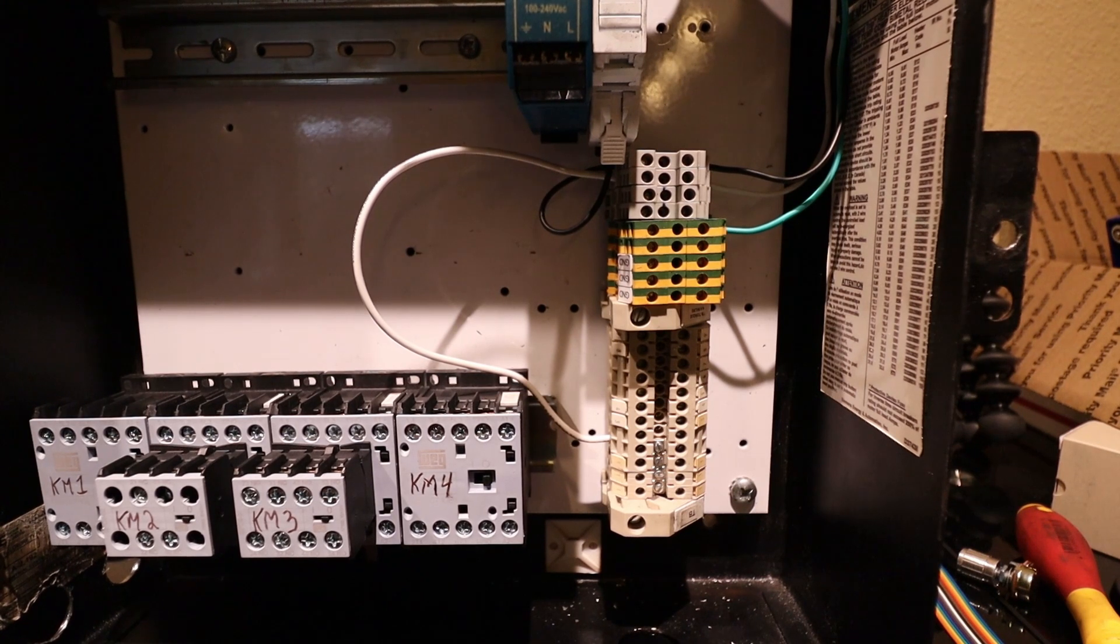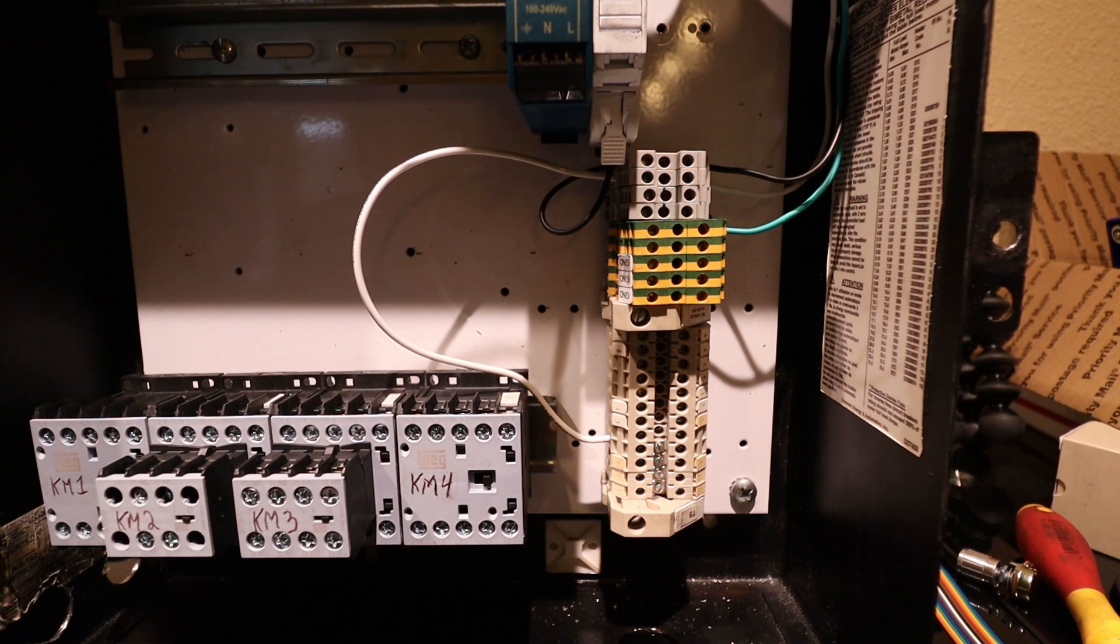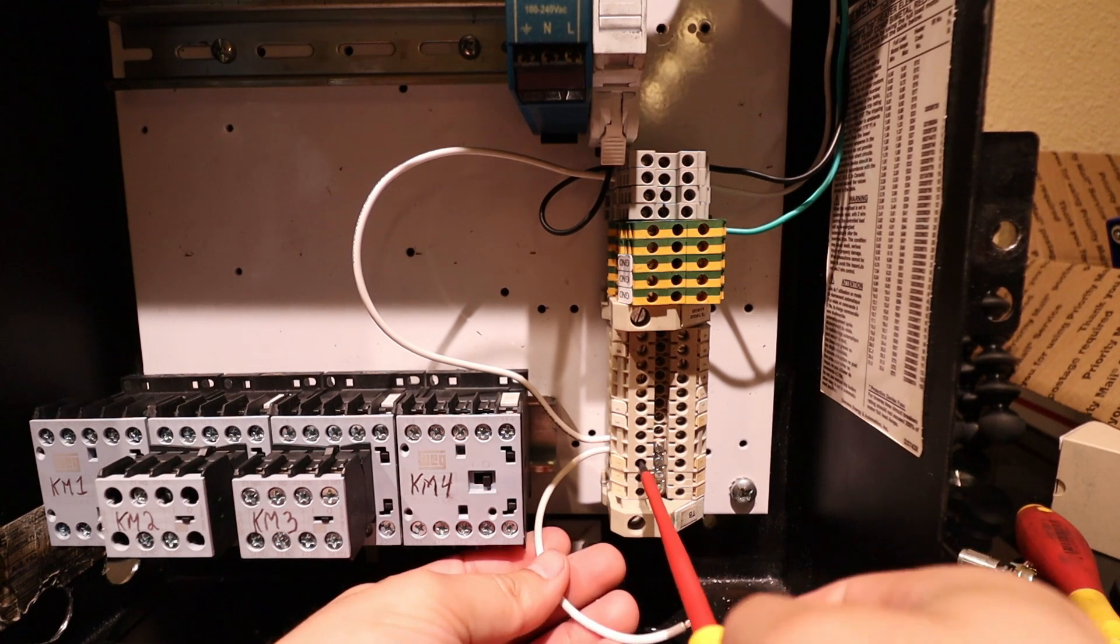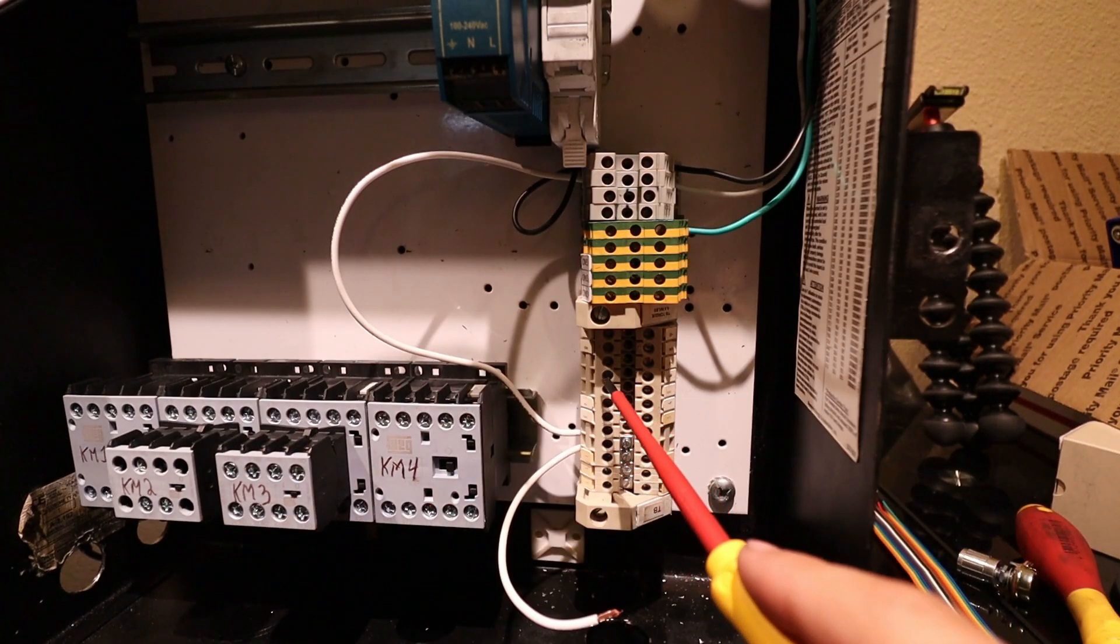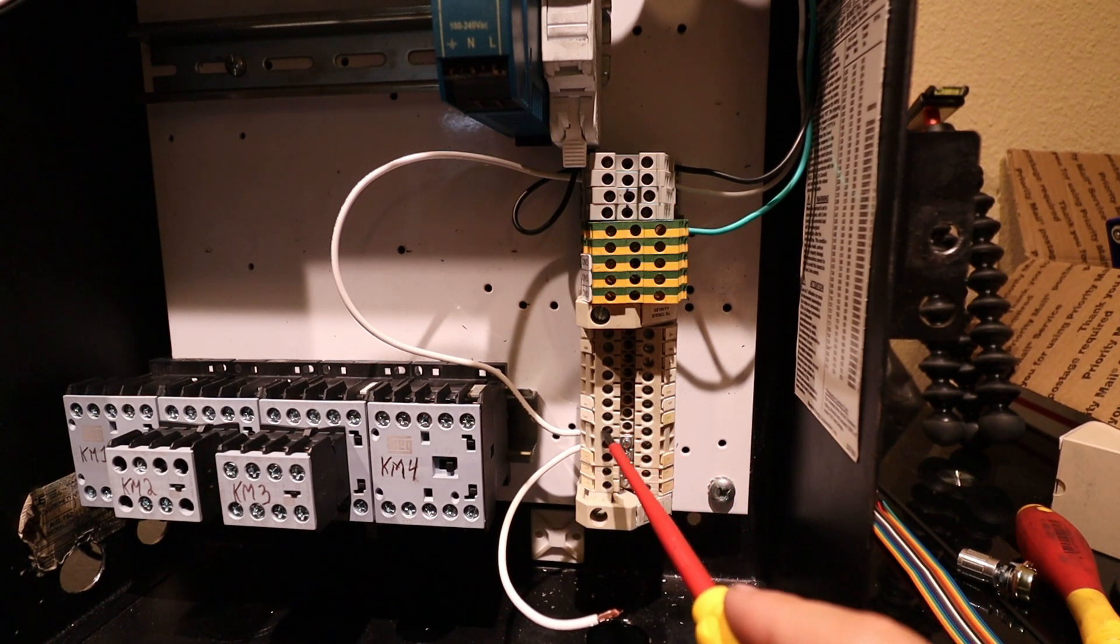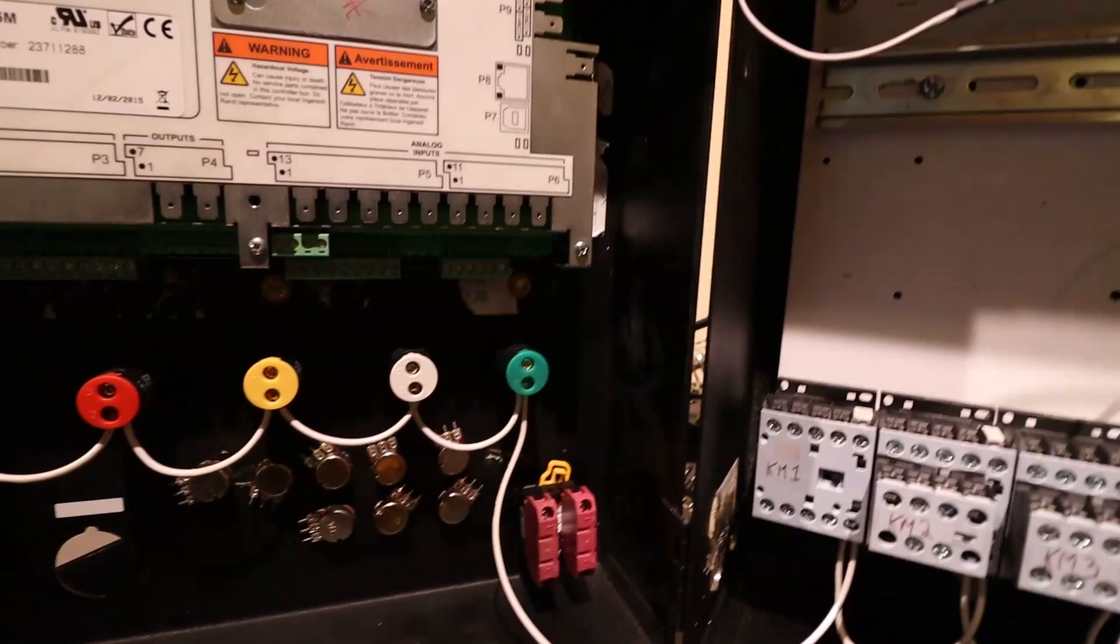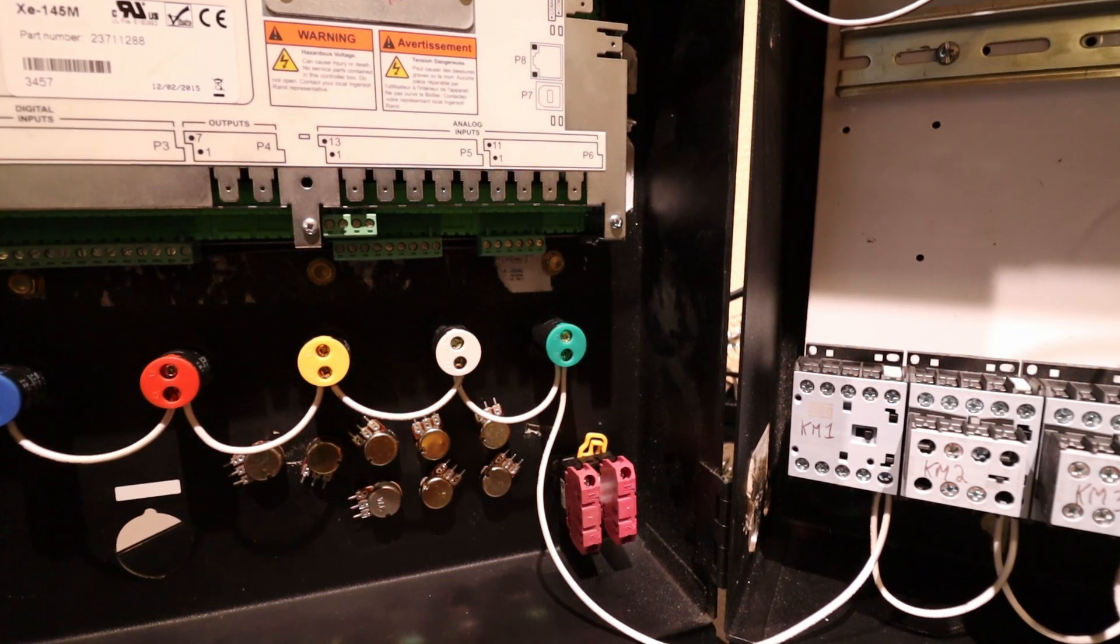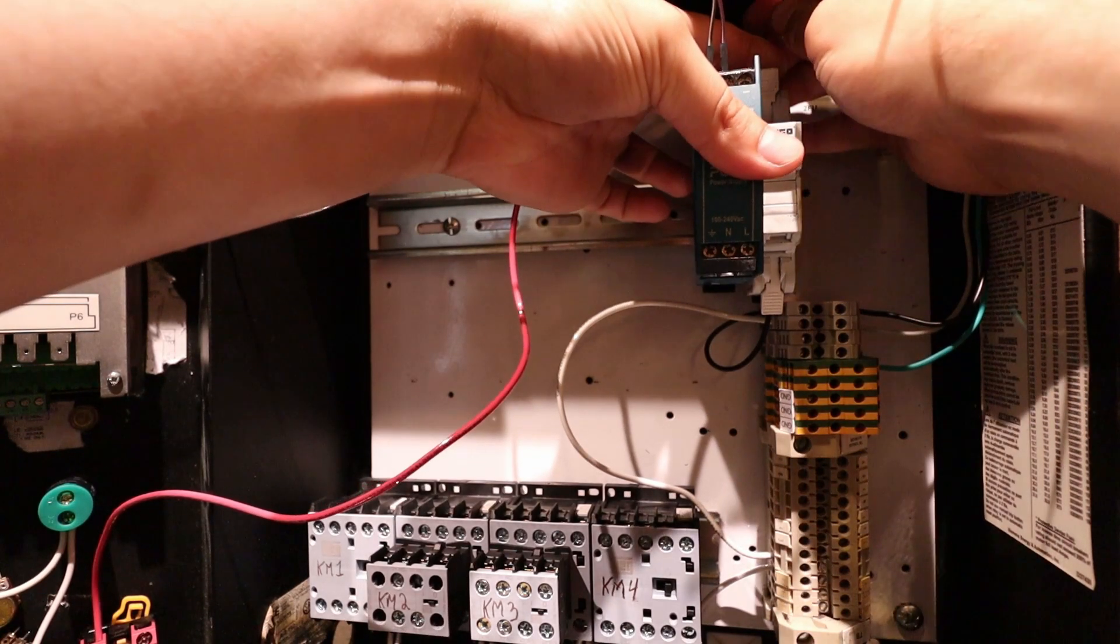Sending that neutral down to the last four terminals on this terminal board. As you can see, they're all connected by these four metal pieces that connect them all together, so the four on the left on the bottom and the four on the right of the bottom are all connected in a group of eight, so the neutrals are all interconnected. If they don't have the strips up top as shown, they're just connected across each other, only not in groups of four. All these white wires shown are connecting the neutral to the contactors and all the way over to the indicator lights. All of these pieces that are connected take 120 volts.